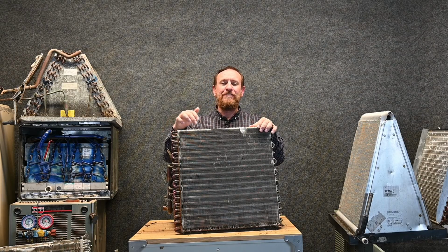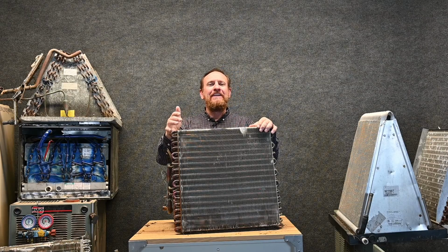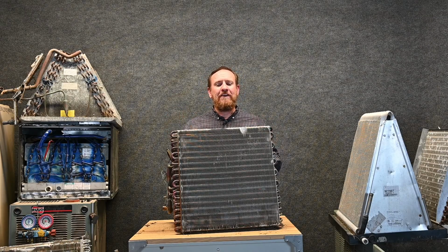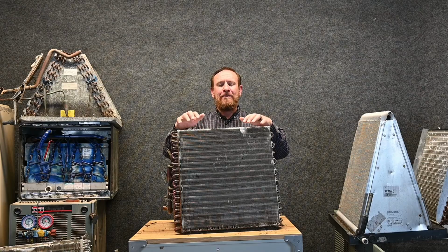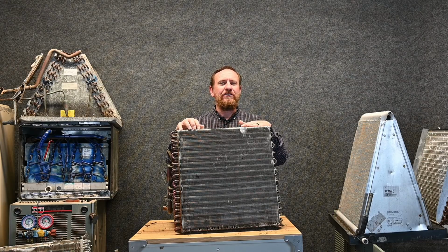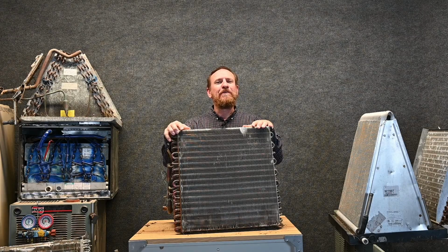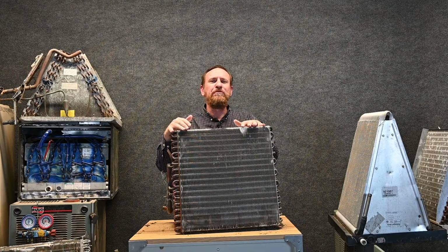They found out that the refrigerant's leaking from the inside out, and they're finding out that it's acid. So we have a few different things going on. Let's talk about the acid one first, because that one we know we can solve. If the installer does a proper pressure test and pulls a proper vacuum, there should never be moisture in that system. But if that installer goes with, well, it's close enough, then we have an issue.